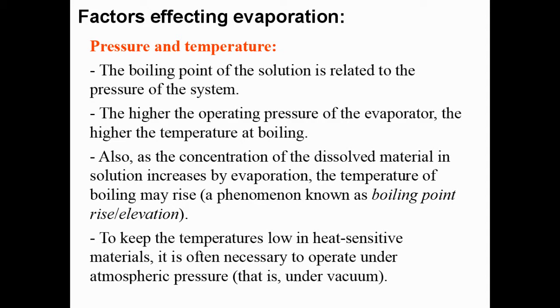Another factor is pressure and temperature. The boiling point of the solution is related to the pressure of the system — the higher the operating pressure of the evaporator, the higher the temperature at boiling. Also, as the concentration of dissolved material increases by evaporation, the boiling temperature may raise — this phenomenon is known as boiling point rise or elevation. To keep the temperature low for heat-sensitive materials, it is often necessary to operate under vacuum, which reduces the boiling point of the liquid.